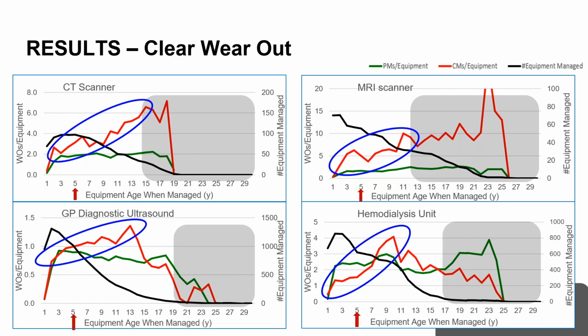CT scanners, as you can see, the number of CMs increase with time. Don't worry too much about the first year. The first year, there is a mixture of warranty, repair, and it's a very confusing situation, okay? And so quite often it's also fractional information. But CT scanner clearly rises the number of repairs up to 15 years, and even perhaps beyond a little bit. Whereas the useful life recommended by American Hospital Association is only 5 years. But we clearly see a lot of CTs used well over 10 years.